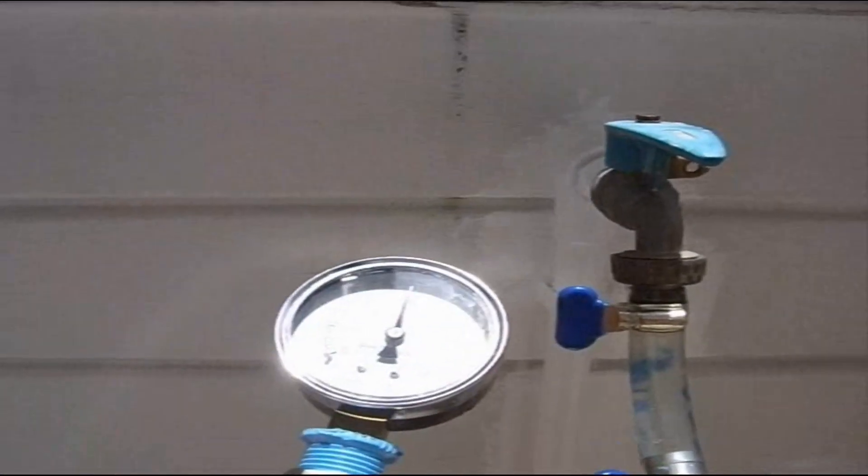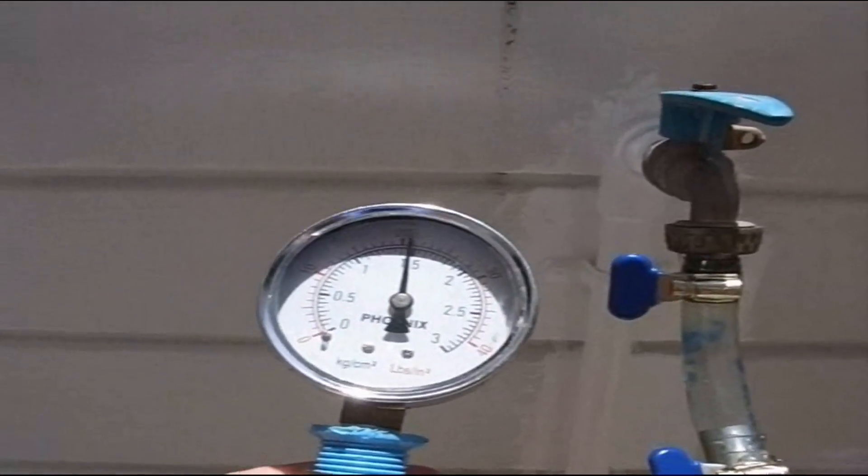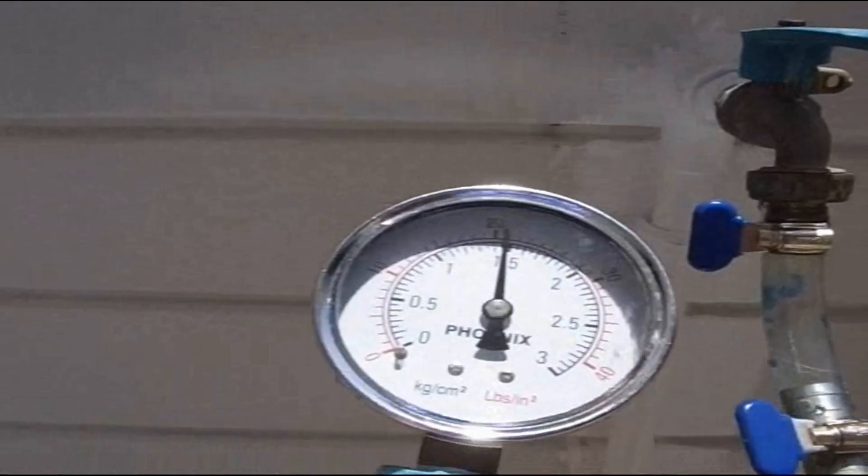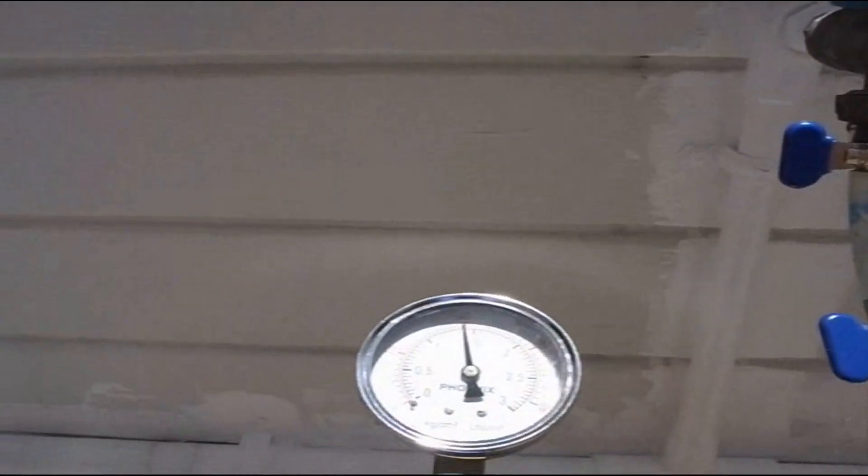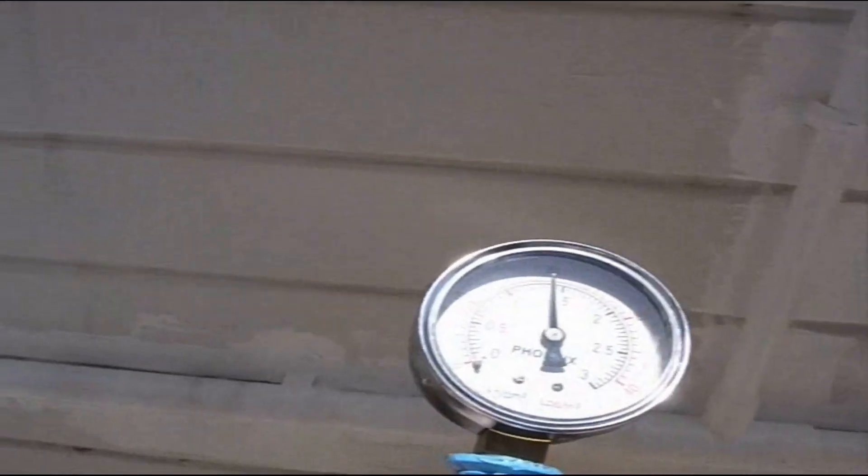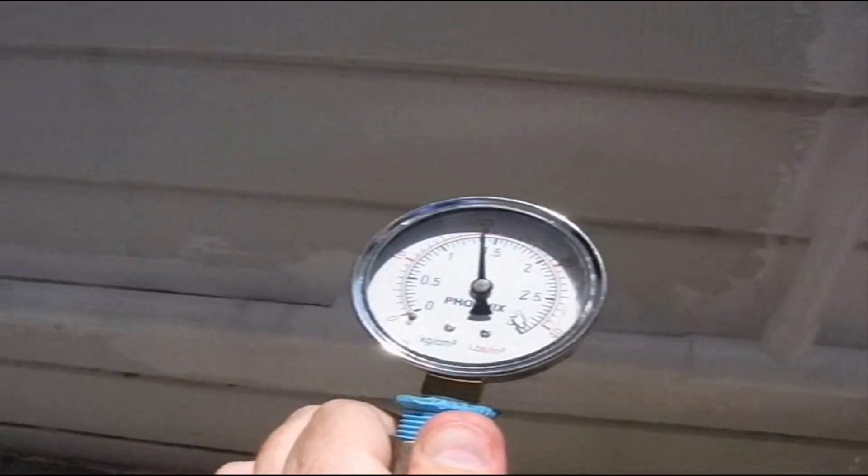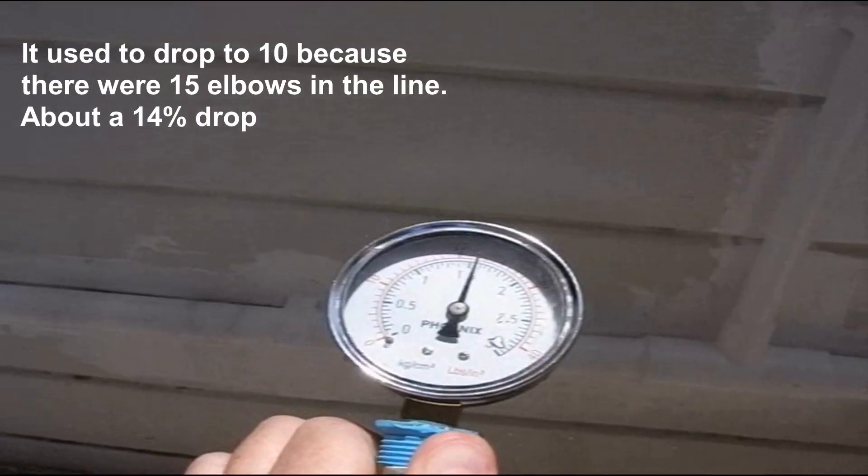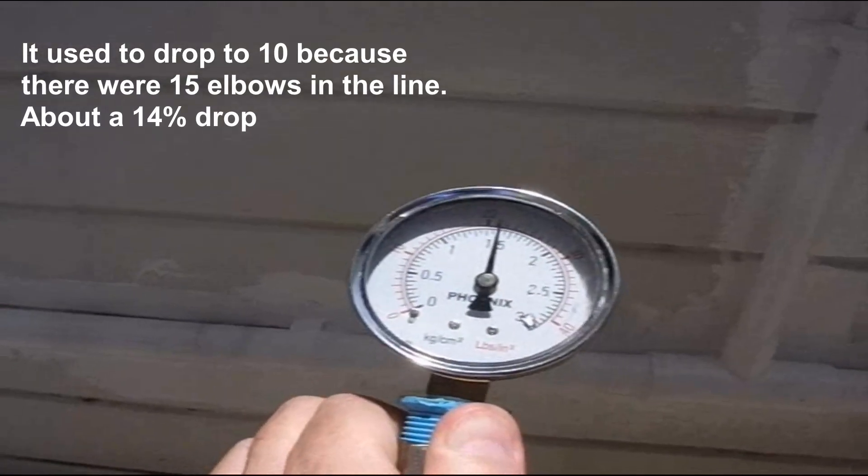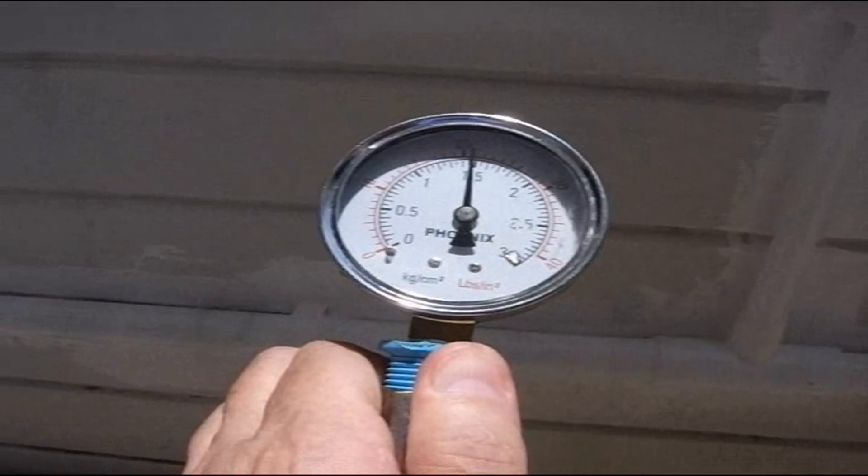Let's see what it looks like with the valve open here. It looks like about 21, stabilizing about 21. It's hard to see, it's bright. When I turn on the opening in the back and look at the dynamic pressure, it drops down to about 18, 19. That gives me an idea of the friction on the pipe. Let's go look at some others.